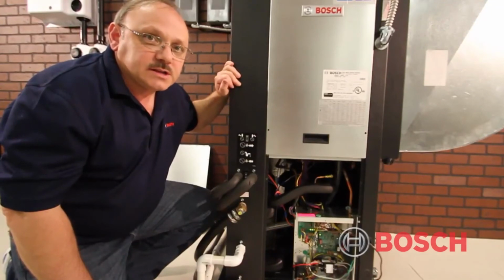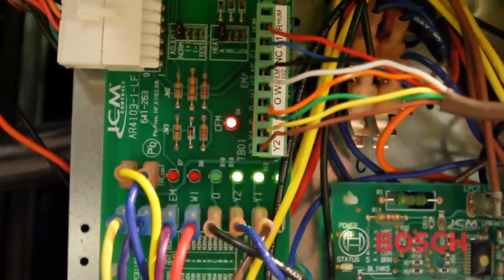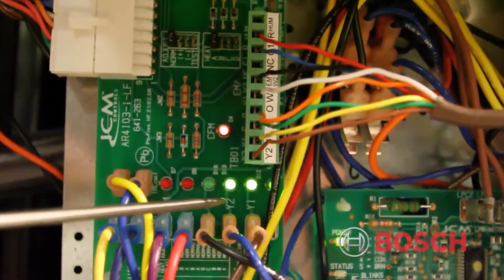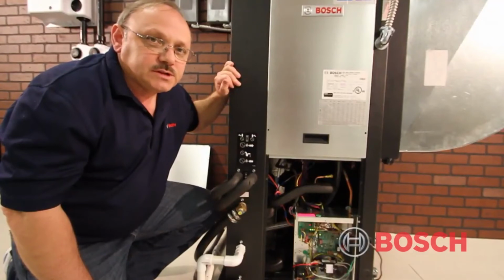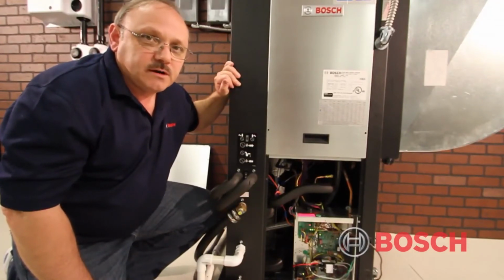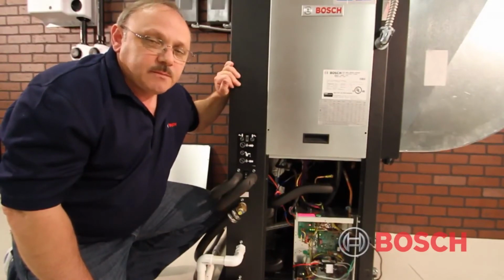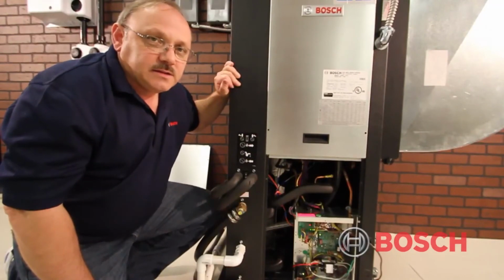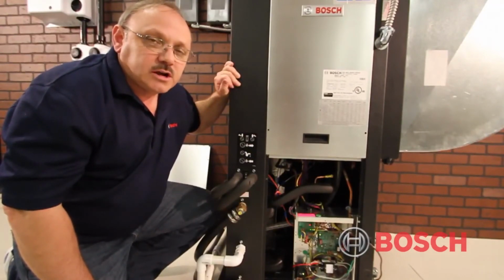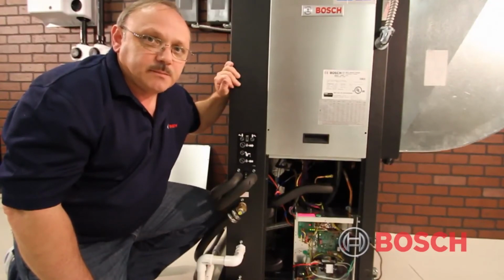We're currently operating in second stage cooling, and a simple way to verify that the thermostat is calling for the correct mode of operation is to look at the LEDs on the ECM control board. There are LEDs outside each terminal designation, whether it be G for fan, Y1 for first stage, Y2 for second stage, and O for reversing valve operation. We can quickly look at the lights to determine the mode of operation. Just because the lights indicate that is the mode of operation it should be in, we always want to verify that we are in second stage by checking the current draw on the compressor. In second stage, the current draw will be approximately 25% higher than it is in first stage. Once we've verified that we're in second stage of operation, we can continue with our water side diagnostics.